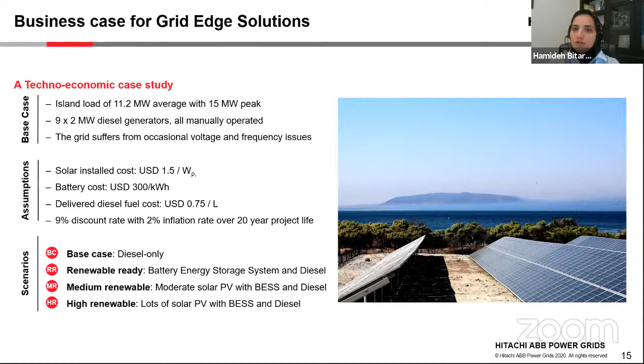Let's dig into the different scenarios and then discuss the results. In the base case, which is diesel only, the grid is powered exclusively by diesel generators. During peak daytime, 8 of them need to be on, and 1 needs to act as reserve, shown as the red diesel generator symbol.